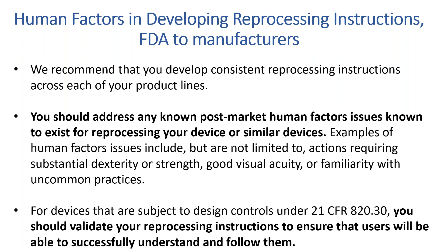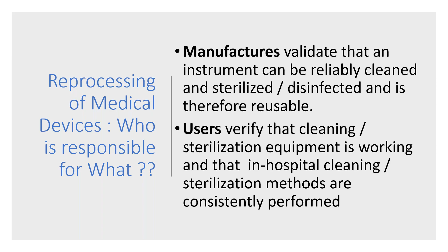For devices that are subject to design control under 21 Code of Federal Regulations, you should validate your reprocessing instructions to ensure that the user will be able to successfully clean the device. So basically, the validation of surgical instruments is really the responsibility of the manufacturer. The manufacturer is responsible to validate instruments' reliability for cleaning, sterilization, and disinfection. But users really need to verify that cleaning and sterilization equipment is working all the time and being cleaned.